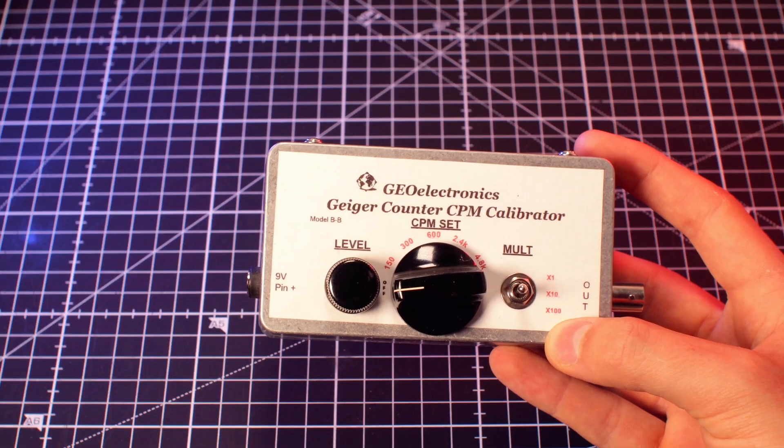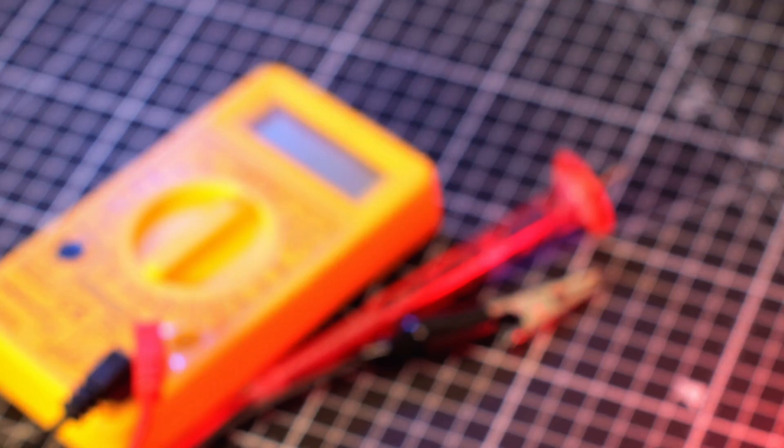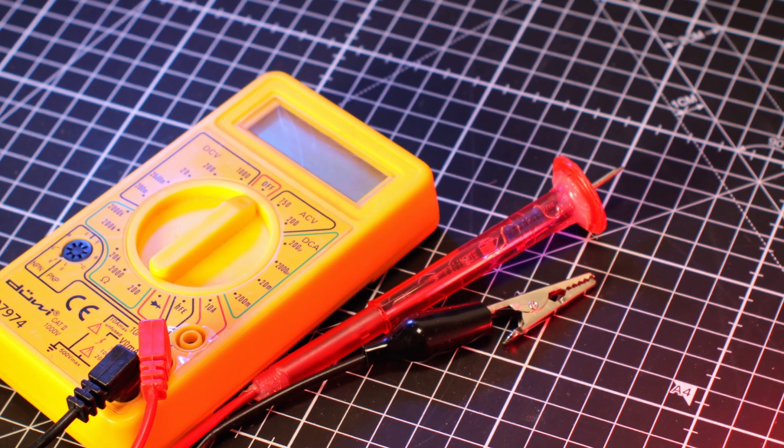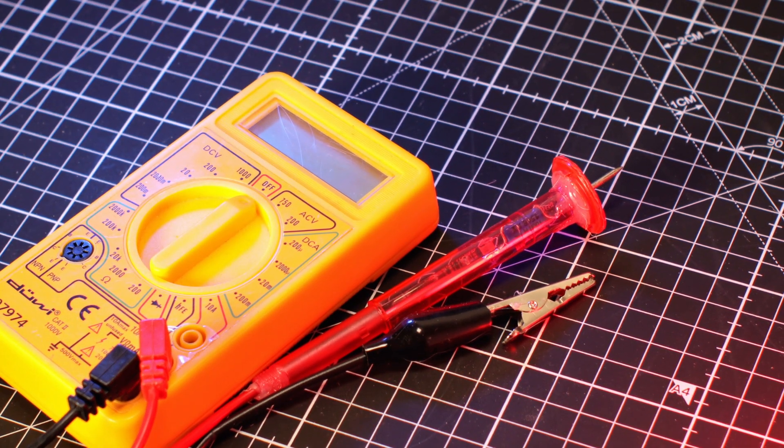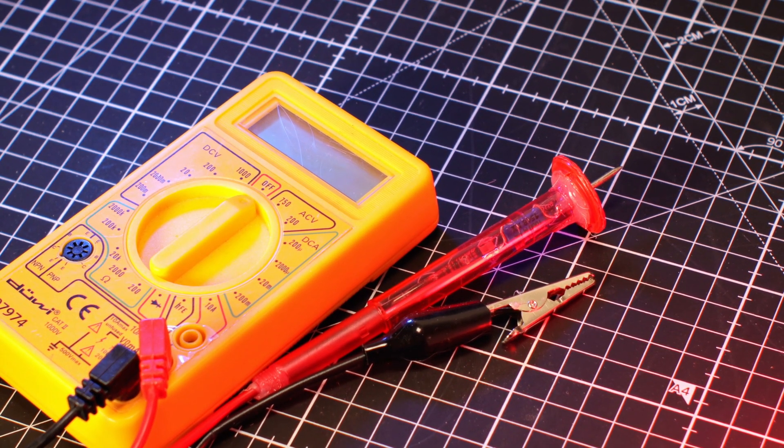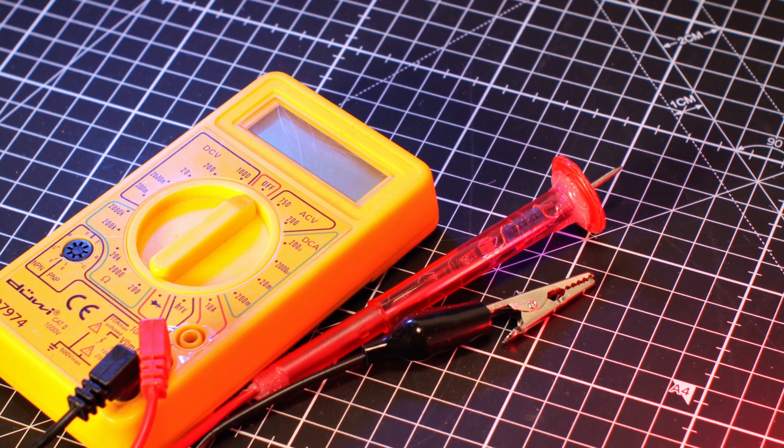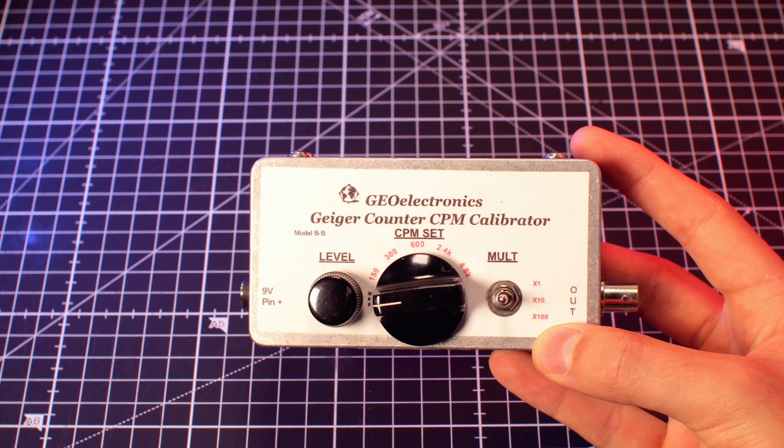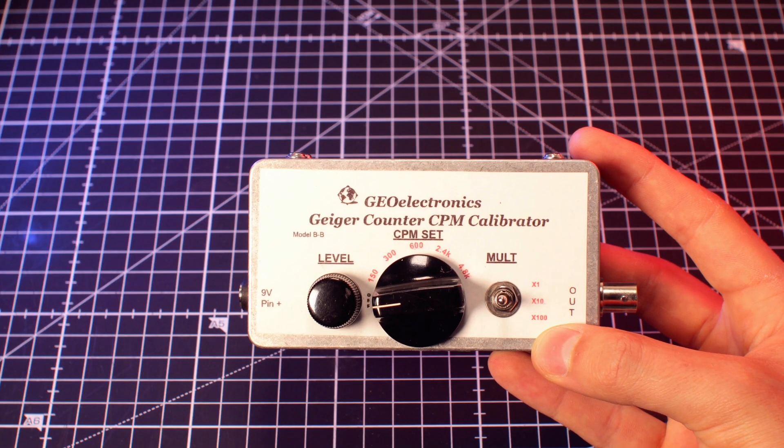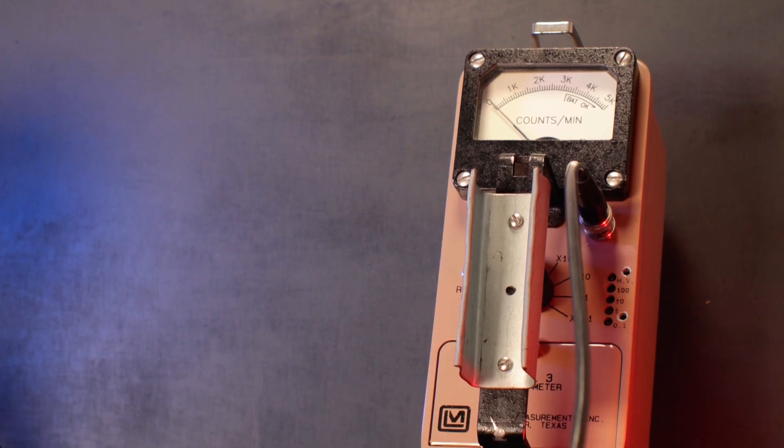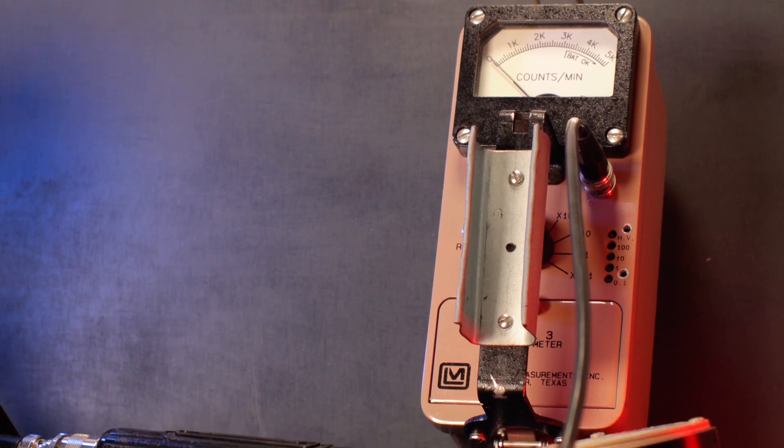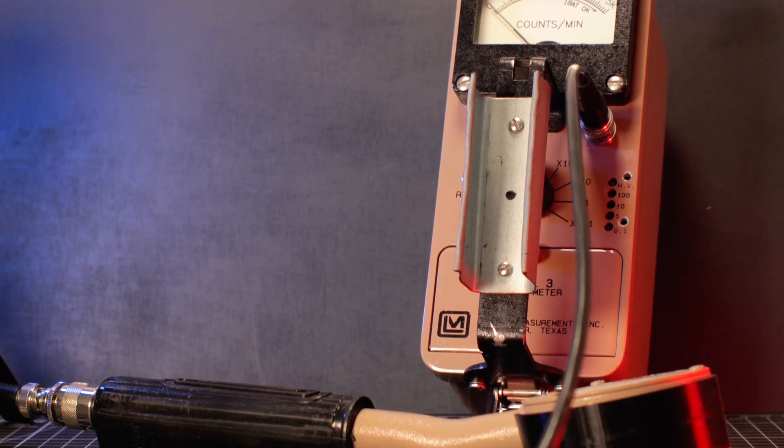In order to do this you will need a multimeter with two probes and a 1 Giga ohm resistor for measuring the high voltage, a pulser and your Geiger counter with a cable to connect a GM probe.